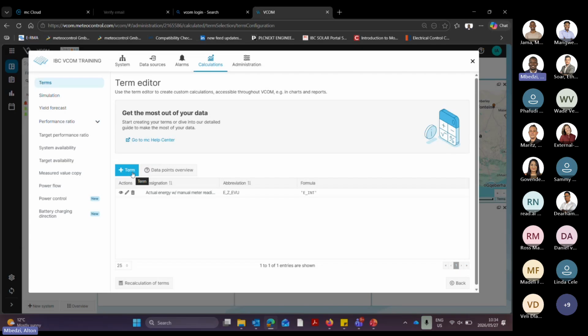We can take a feed-in import meter sitting perhaps on one side of the mall, and a plant sitting on the far right, with another on the far left of the mall, which gives you two tying points. We're able to create a self-consumption graph and power flow based on that feed-in meter, which is your main meter, and the two subsystems currently on site.